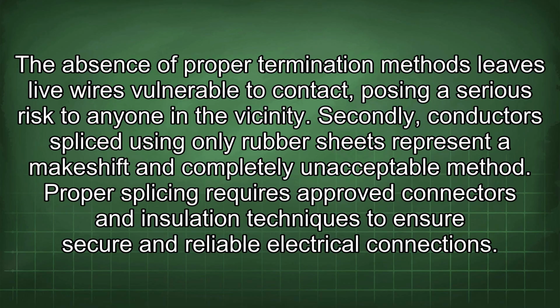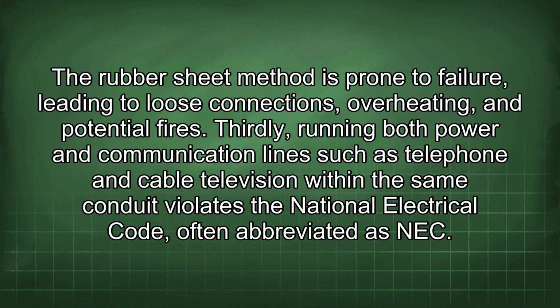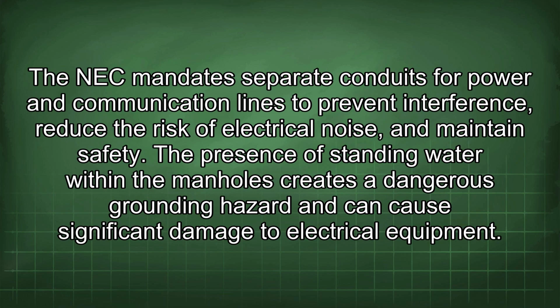Proper splicing requires approved connectors and insulation techniques to ensure secure and reliable electrical connections. The rubber sheet method is prone to failure, leading to loose connections, overheating, and potential fires. Thirdly, running both power and communication lines such as telephone and cable television within the same conduit violates the National Electrical Code, often abbreviated as NEC.